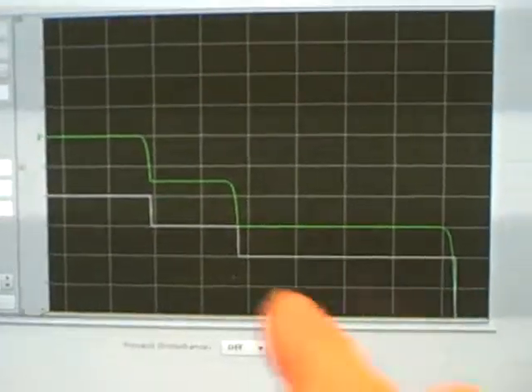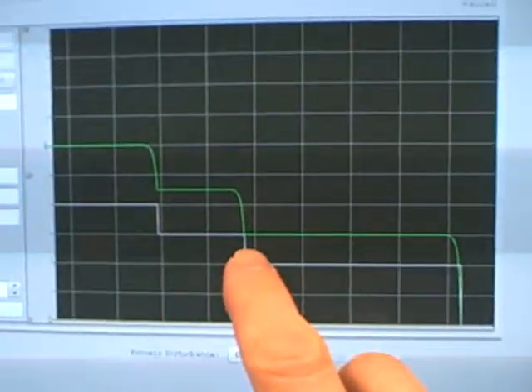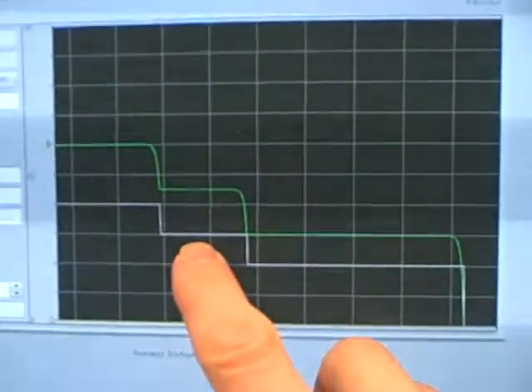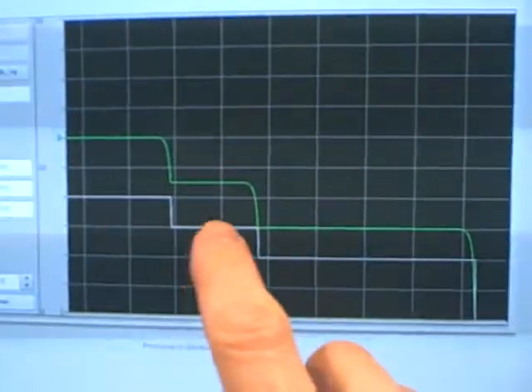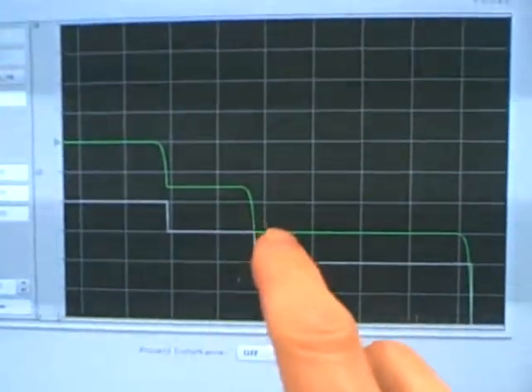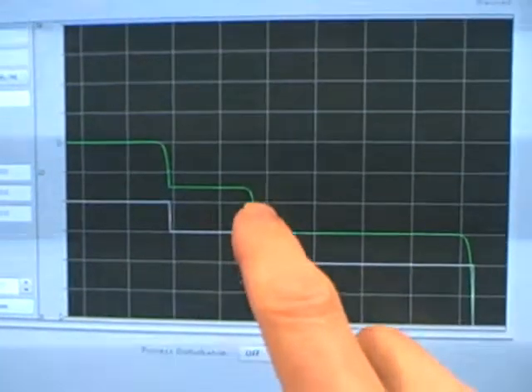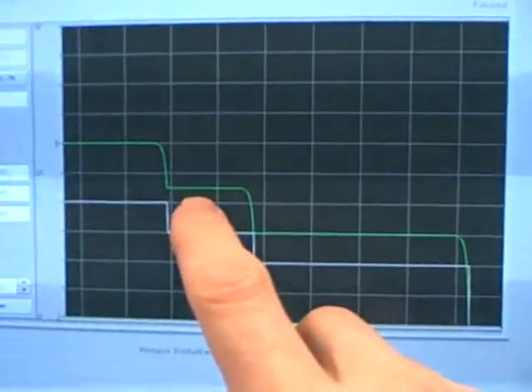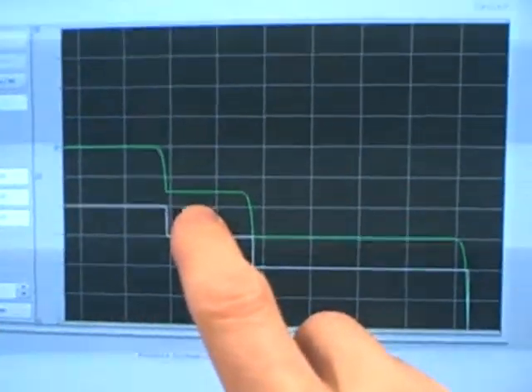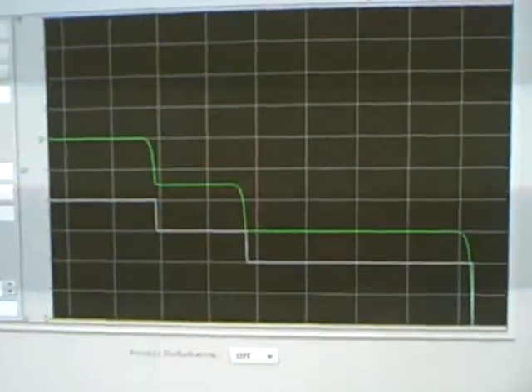I'm going to pause the simulation right now and comment on this. So we've made two output step changes, one from 20% to 30%, one from 30% to 40%. In each case, the process variable made a corresponding step change and it settled to a new value. We refer to this as self-regulation.